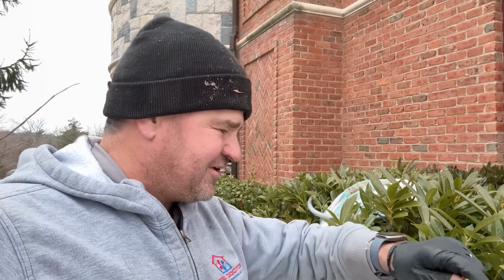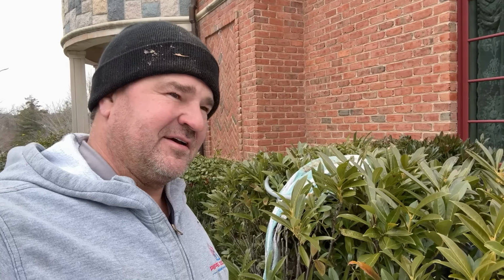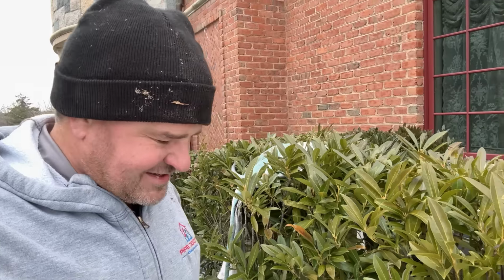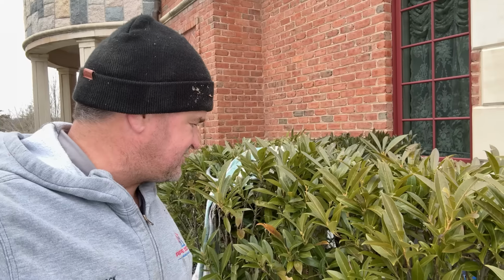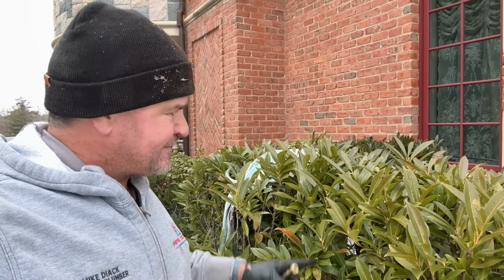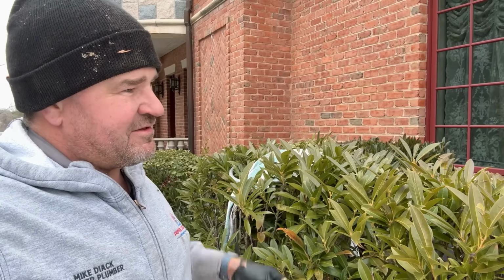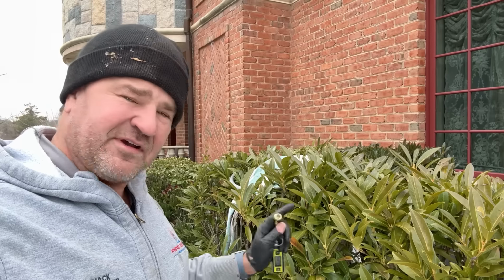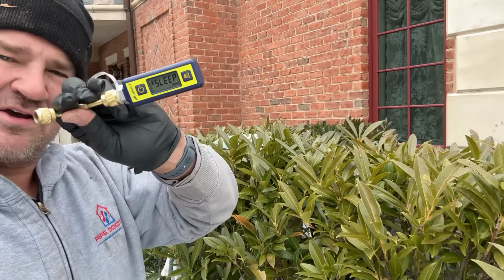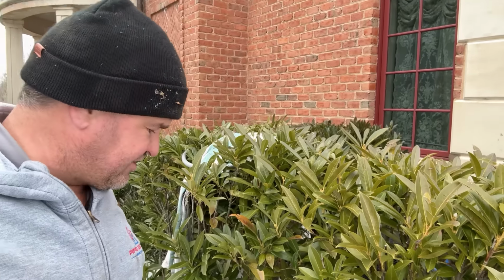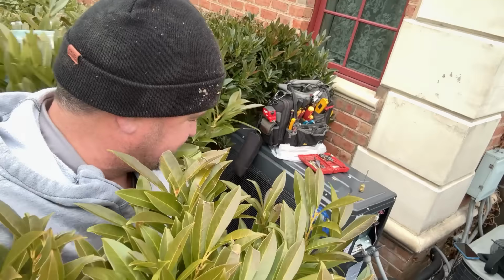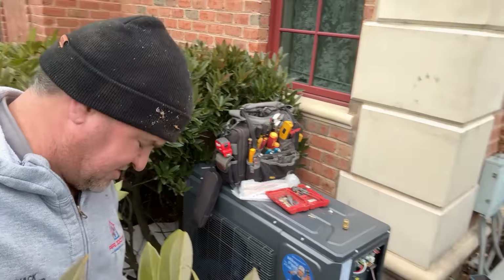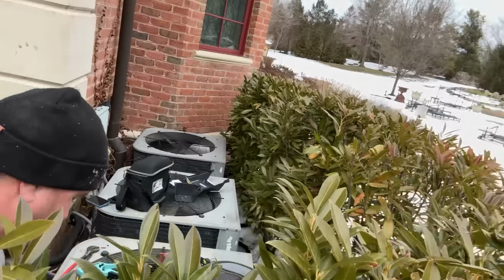It's cold, it's 41, so it could be colder. But I helped Derek connect a bunch of 8 and 6-inch flexible connectors to the takeoffs on the supply plenum. Daniel and Derek are up now in the attic. We're pulling a vacuum, and I've got my BluVac+ Micron gauge. Let's go see what's going on, because this is one of the most important parts of commissioning your equipment.